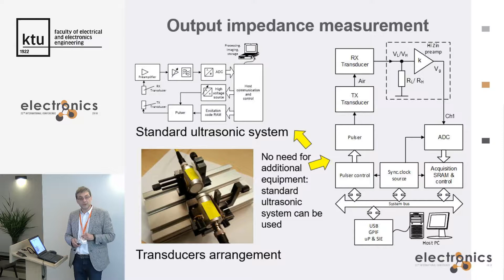So we need a PC to control what we are sending, then the controller of the pulser, then the pulser itself, the transmitting transducer, receiving transducer, the preamplifier, AD converter, and of course acquisition, buffer memory, and everything goes to the PC. If you compare to a conventional ultrasonic non-destructive testing system setup, you can see that everything is the same. In an ultrasonic system, we always have the excitation channel and the reception channel, because those are used both for imaging and for transmission measurements. So that's one more advantage, because we don't need additional instrumentation to do the measurements. We can use the same ultrasonic system for the measurements.